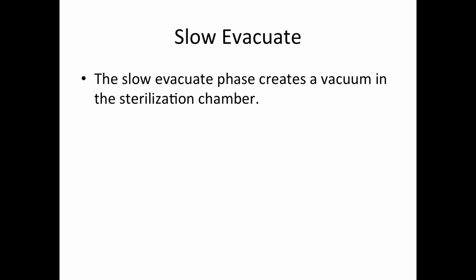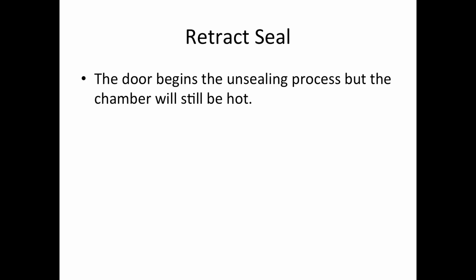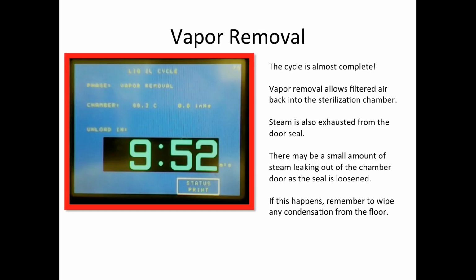During the slow evacuate, we create a vacuum in the sterilization chamber. And during the retract seal phase, the unsealing process begins, but the chamber is still going to be hot. Vapor removal. Remember, we have created a vacuum in the sterilization chamber. So we've sucked out any residual steam, we've sucked out any fumes, any bad smells maybe from something that got hot.